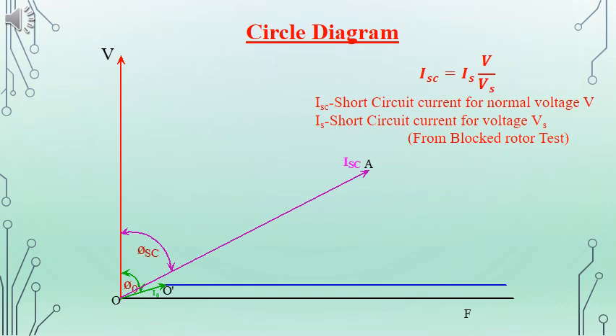For drawing the circle diagram, we require the short circuit test as well as the open circuit or no-load test results, along with the blocked rotor test results. ISC is the blocked rotor test current corresponding to the normal voltage of the machine, and we have the power factor angle on the short circuit test. I0 is the no-load current and its power factor angle is from the no-load test.